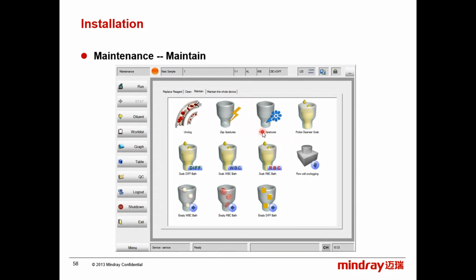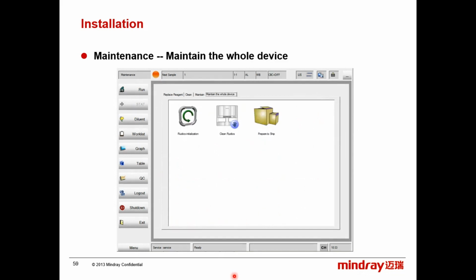So here you can zap the apertures to burn this. This is flush the apertures. Probe cleanser soaking: here you use probe cleanser. Diff bath soaking, WBC bath soaking, RBC bath soaking, flow cell unclogging. And this is for the emptying of the bath. Okay, this is for whole device maintenance. You can do fluidic initialization. If you skip it for some error, you can come here directly and initialize fluidics. It is the startup sequence. This cleans all the fluidics, and this is prepare to ship.